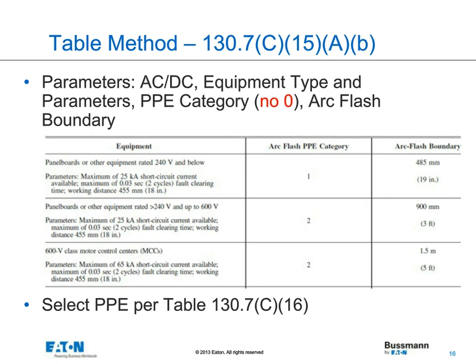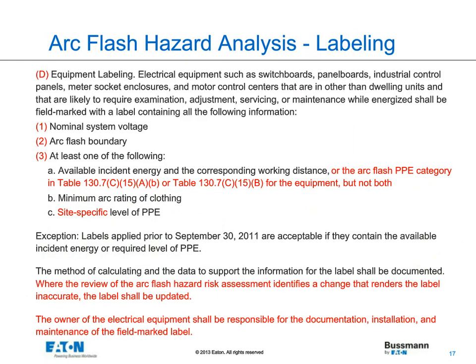You'd have an arc flash boundary of 19 inches. An important thing to note here is that there is no category 0 anymore. It's just either a 1, 2, 3, or 4. So they did eliminate the HRC 0, if you will. And then, of course, we would select PPE per Table 130.7(C)(16). That tells us how to best dress based upon a given PPE category.